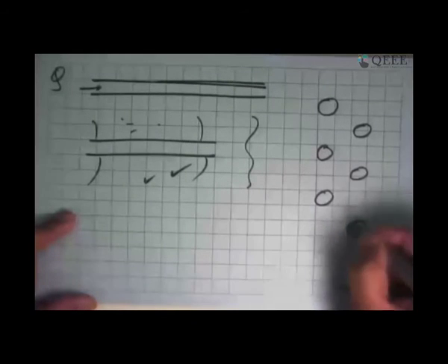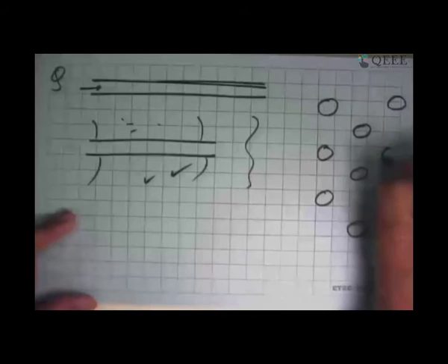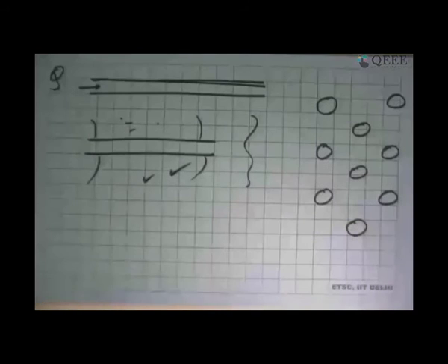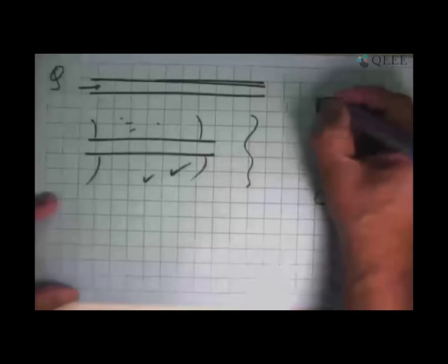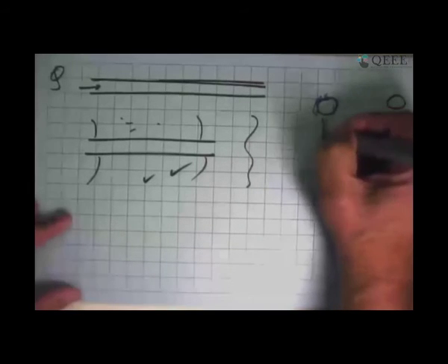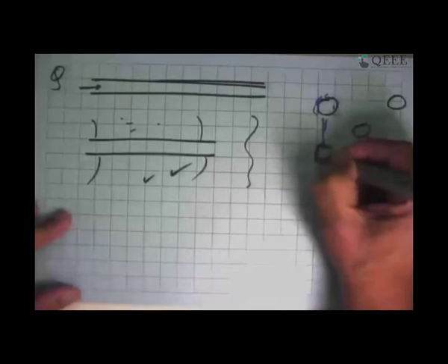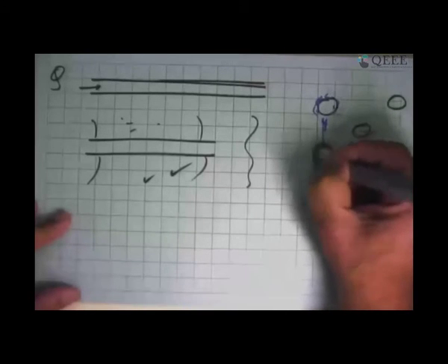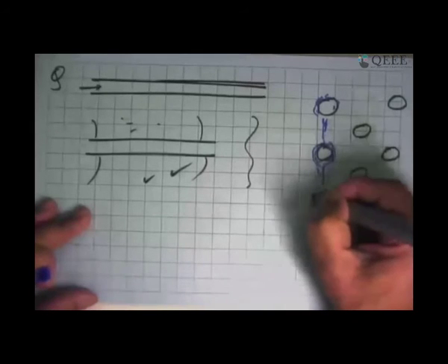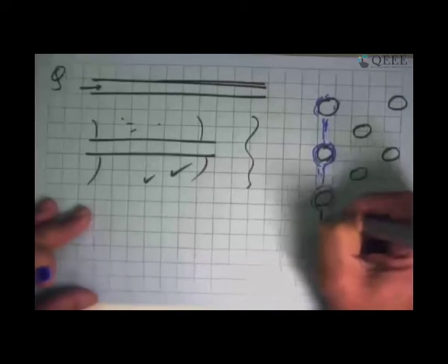and say, well, and build a whole tube bank. And so, well, now what happens? How do I predict average heat transfer for all these tubes? Well, what we have to recognize is that when we do that, something condensed over here, this fell off, maybe as a drop or as a stream. It came on this tube, and so now it blanketed this tube, formed a thicker layer of liquid on it.